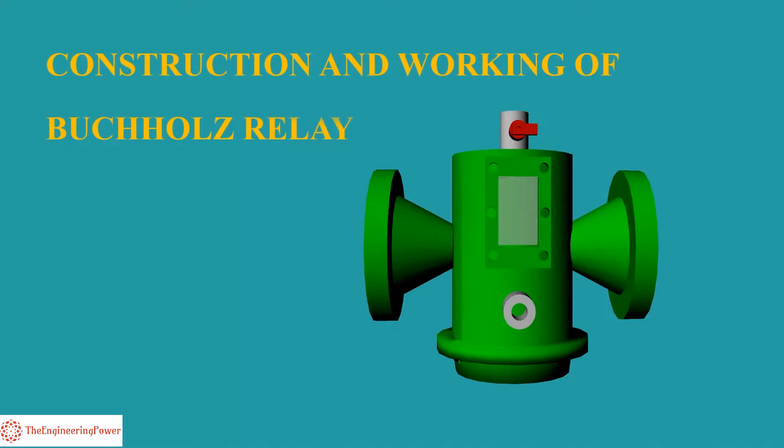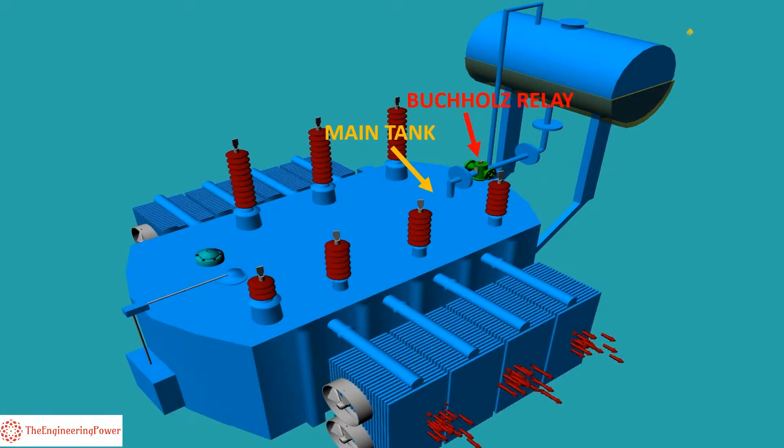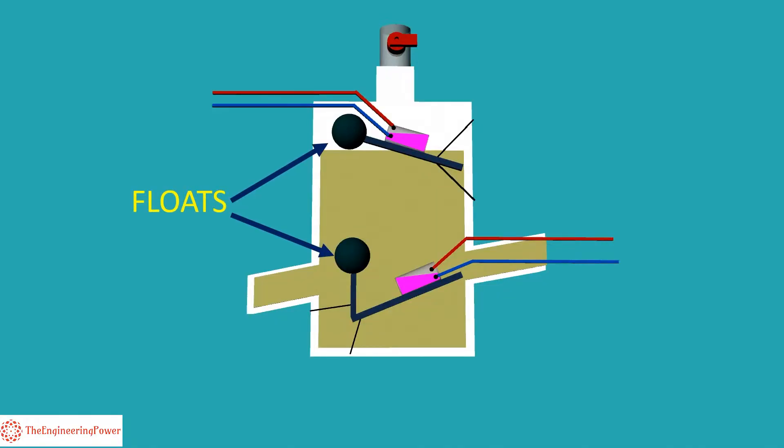Now we explain the construction and working of Buchholz relay. Buchholz relay is installed on the pipe connecting the main tank and conservator tank of the transformer. It has two floats with hinges attached. The upper float is related to the alarm function, whereas the lower float is related to the trip function of the Buchholz relay.